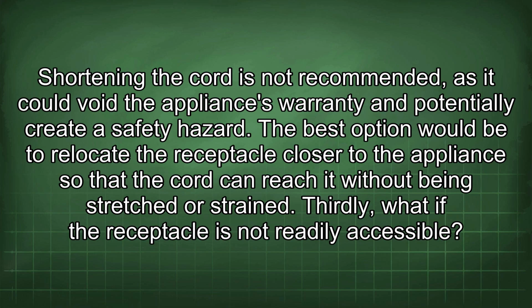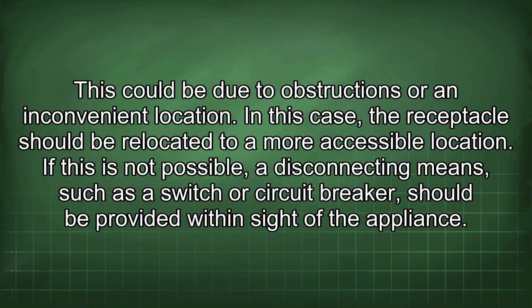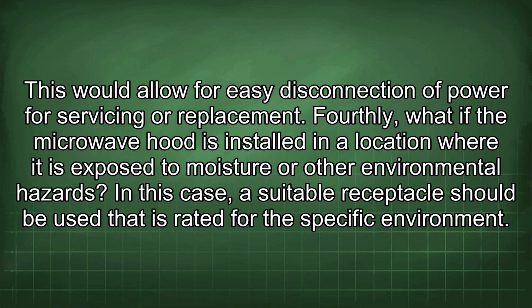Thirdly, what if the receptacle is not readily accessible? This could be due to obstructions or an inconvenient location. In this case, the receptacle should be relocated to a more accessible location. If this is not possible, a disconnecting means such as a switch or circuit breaker should be provided within sight of the appliance. This would allow for easy disconnection of power for servicing or replacement.